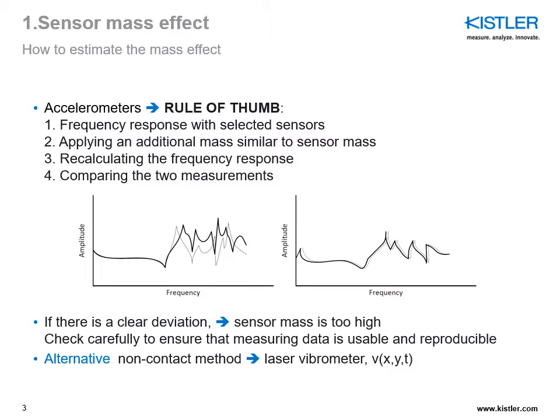How could we estimate that mass effect if we have no clue whether the sensor can be negligible or not? A rule of thumb can be to use a very simple excitation to generate a resonance frequency of the whole system, including your sensor mounted on it. First, you run a small shock test to excite resonance and measure with one selected sensor.